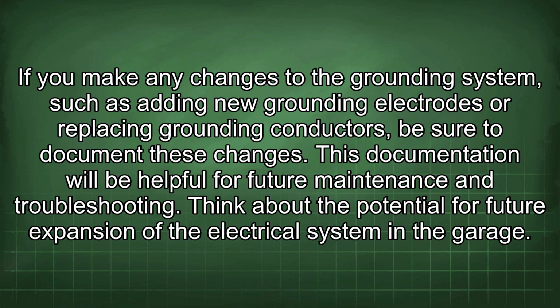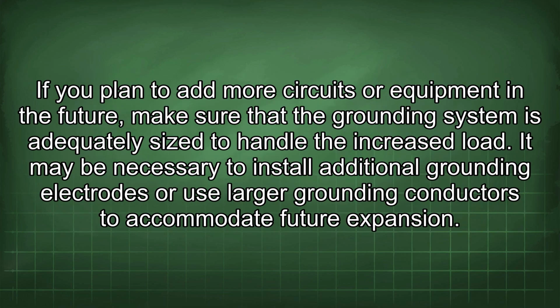Think about the potential for future expansion of the electrical system in the garage. If you plan to add more circuits or equipment in the future, make sure that the grounding system is adequately sized to handle the increased load. It may be necessary to install additional grounding electrodes or use larger grounding conductors to accommodate future expansion.